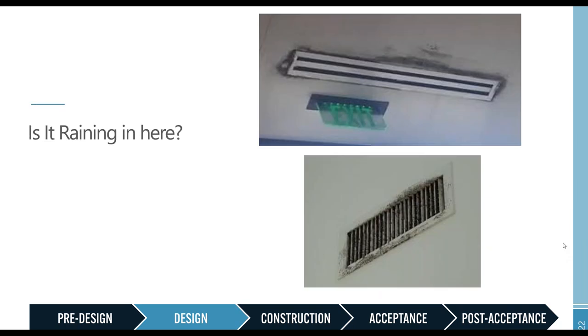So another seemingly simple issue that I encounter is sweating diffusers. And these two images are pretty gross, but typically this occurs when supply diffusers are close to a source of humid air, most commonly an exterior door or operable window, especially here in DC during the swampy summers. Other causes can be issues resulting in lower than expected air temperatures that are caused by airflow issues in the system itself, and that results in condensation on the ducts and diffusers. Regardless, the last thing anybody wants is mold and water damage in their brand new, pretty building.